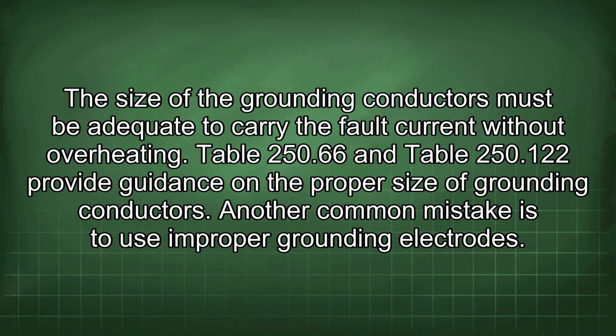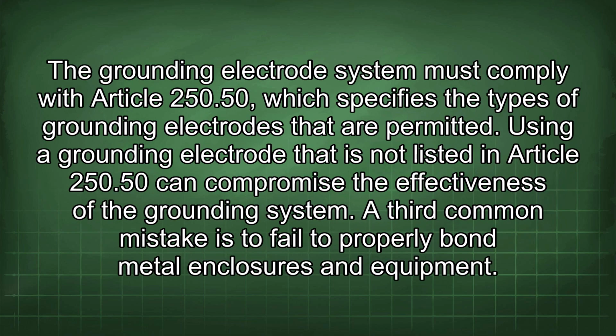Another common mistake is to use improper grounding electrodes. The grounding electrode system must comply with Article 250.50, which specifies the types of grounding electrodes that are permitted. Using a grounding electrode that is not listed in Article 250.50 can compromise the effectiveness of the grounding system.